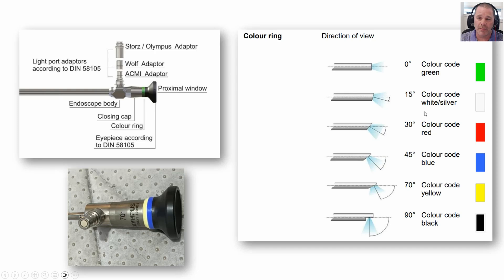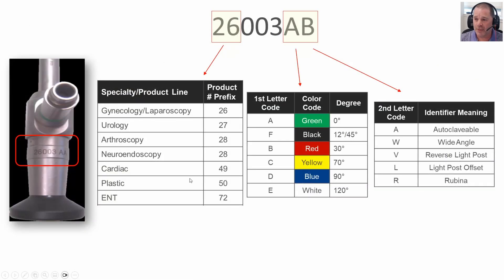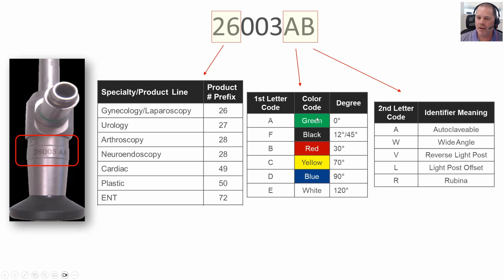Some manufacturers actually use the model number to indicate different things. With this particular manufacturer, the prefix indicates the specialty. They also use the suffix — in this case, the letter 'A' would indicate it's a zero-degree telescope looking straight ahead, and they may indicate that with a green color band ring. Depending on the model of the scope, there are some unique identifiers. For example, if we see a letter 'W' in the middle of the model number, that indicates something unique about the telescope.